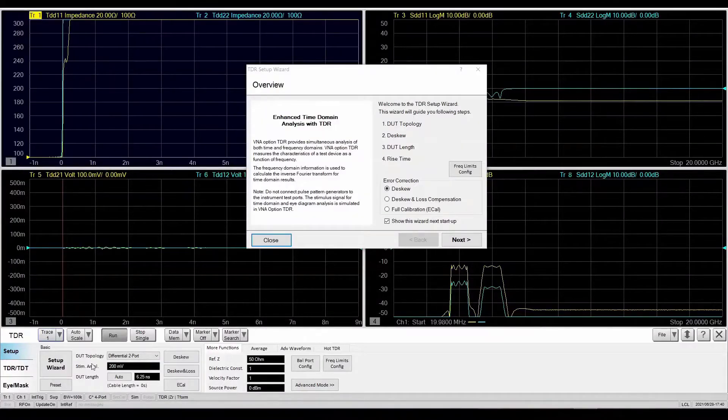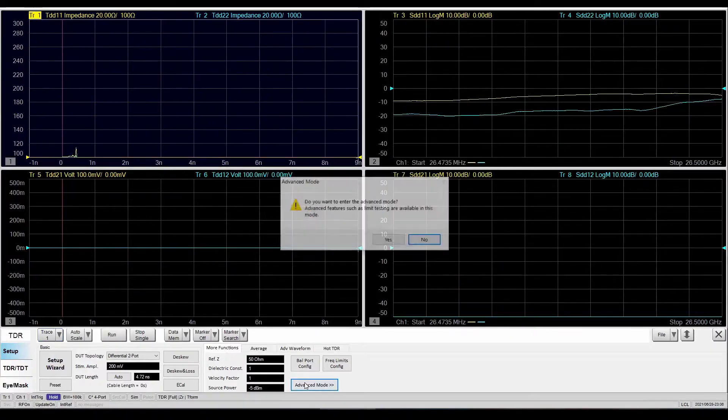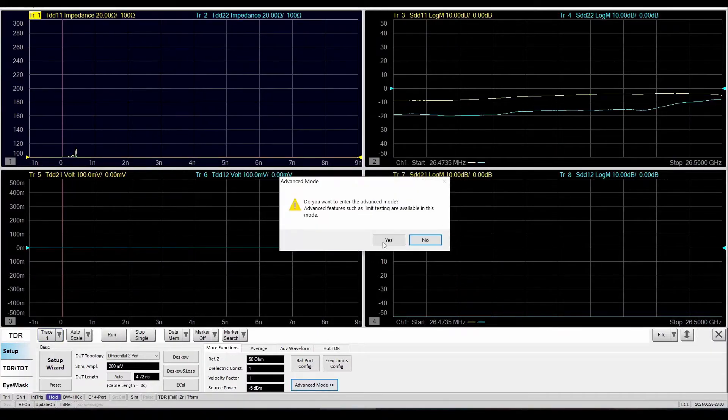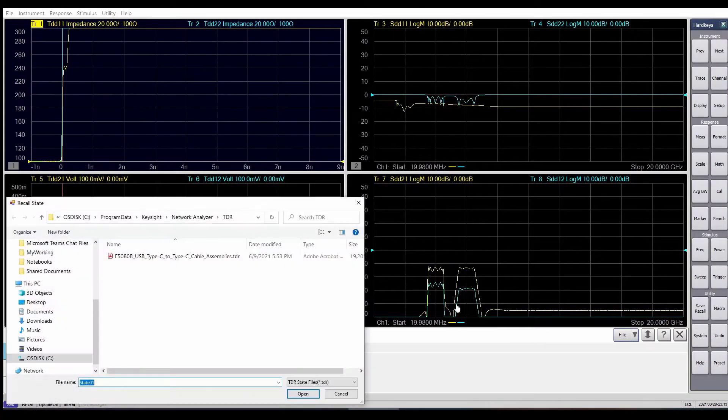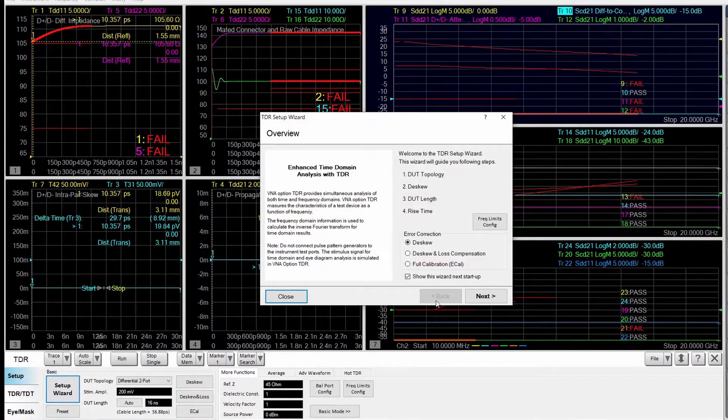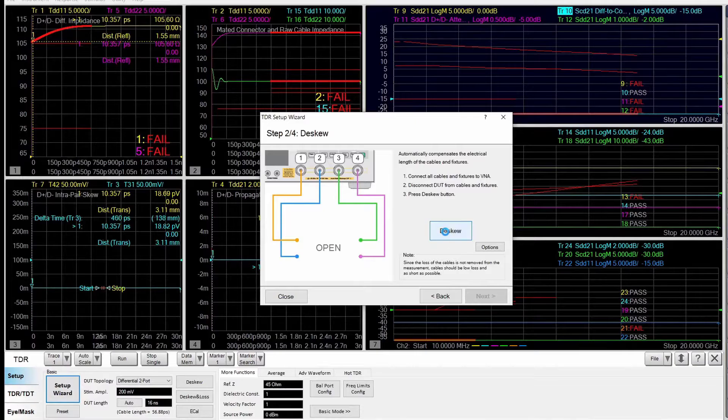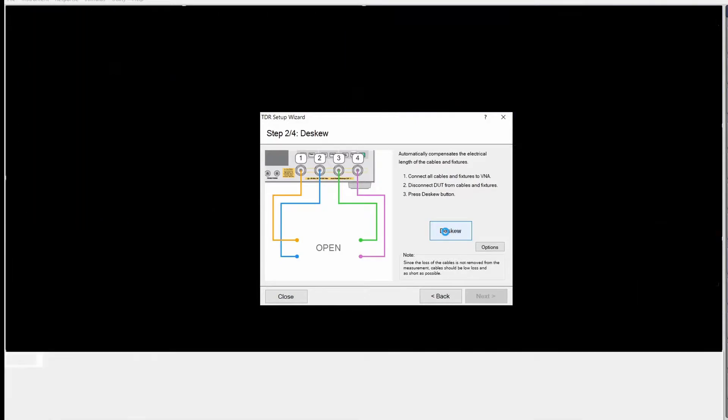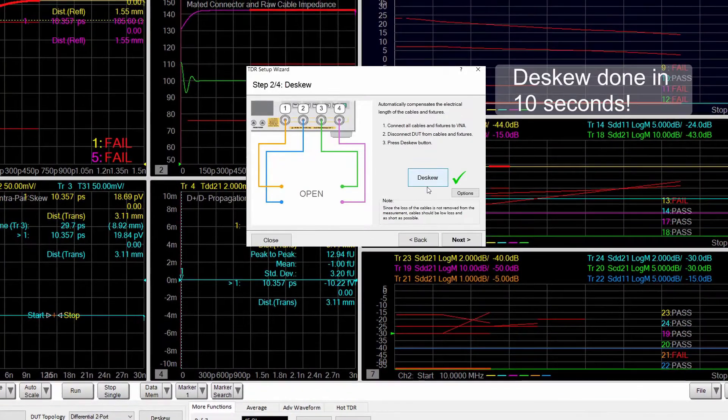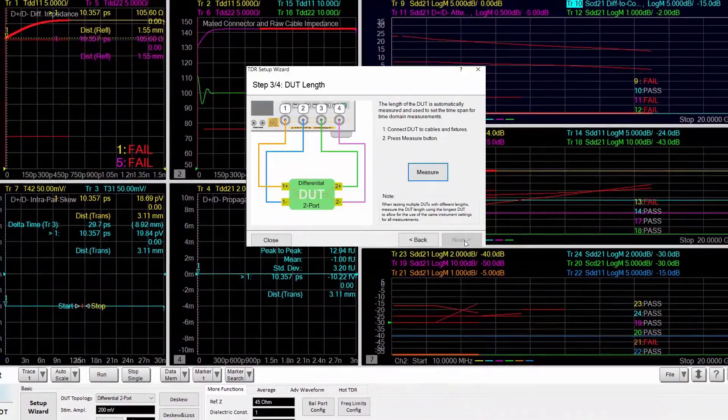First, launch the Enhanced TDR software, go to Advanced mode, and load the USB Type-C compliance test state file that can be downloaded from Keysight.com. Next, go to the setup menu. The simple and intuitive setup wizard will guide you through the steps, including deskew and calibration.